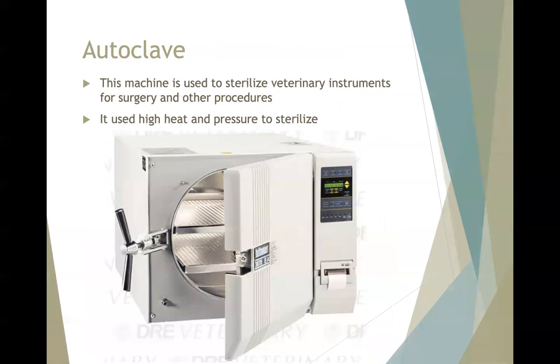This is a steam autoclave. It uses high heat and pressure to sterilize the instruments that we put in there. We can either sterilize packs or pouches, but we never mix the two in a cycle. Packs take significantly longer, anywhere from half an hour to an hour of sterilization, whereas pouches are usually only 5 to 10 minutes. So there are variations in pressure and heat for what you are sterilizing.